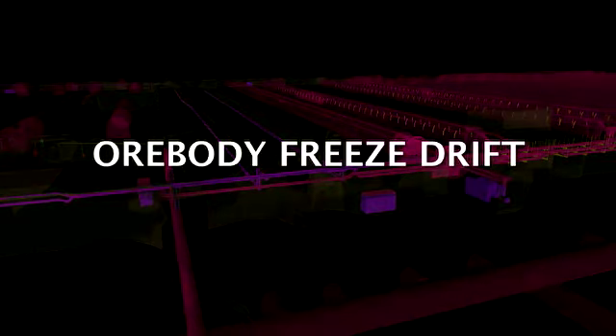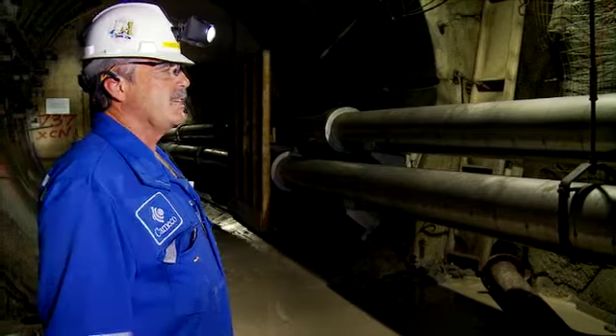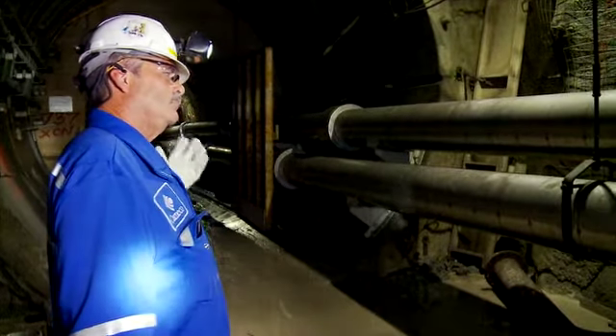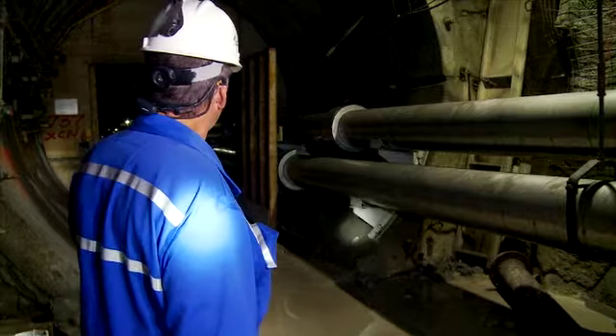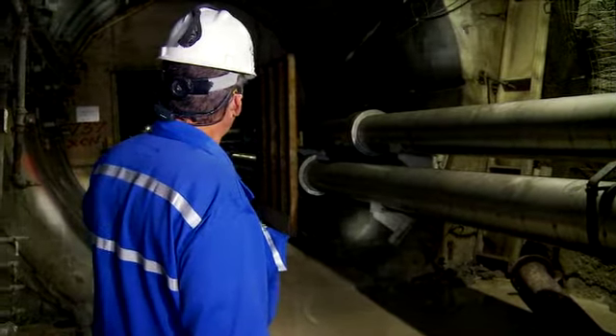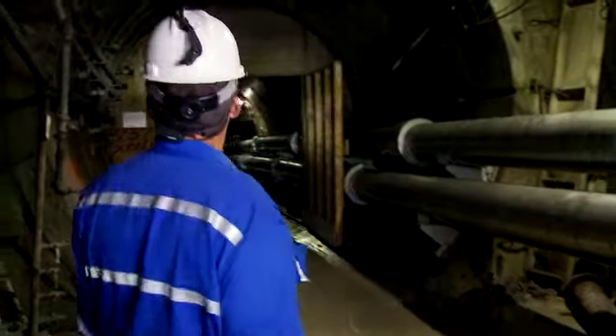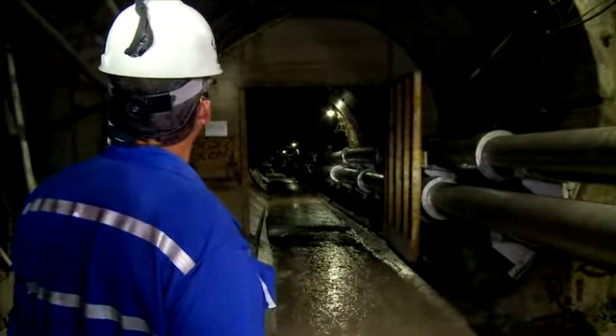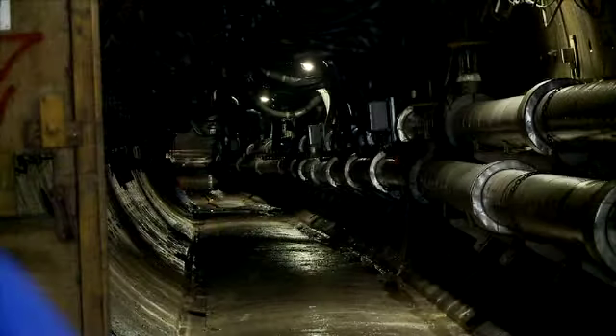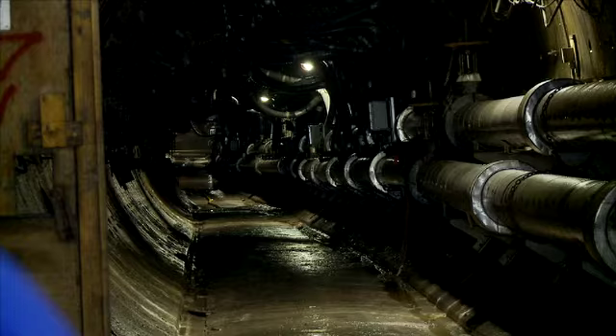Okay, this is 737 Crosscut North. This is our first freeze-hole drift, and done by the tunnel boring machine. We've refurbished the whole area now, and if you look down there, you can see the feed and the return line for the freezing, and then you can make out the rubber pipes, insulated pipes that are going up to the boreholes going into the back, or freeze holes in the back. Very similar to what you saw underneath number 2 shaft area.